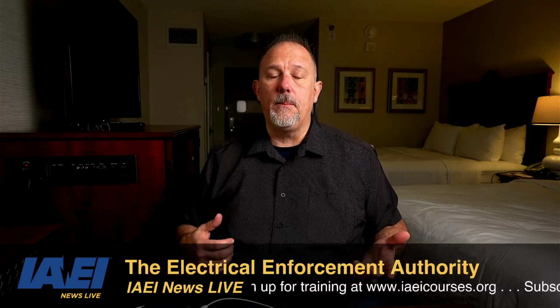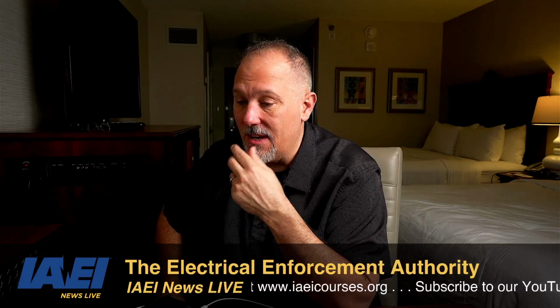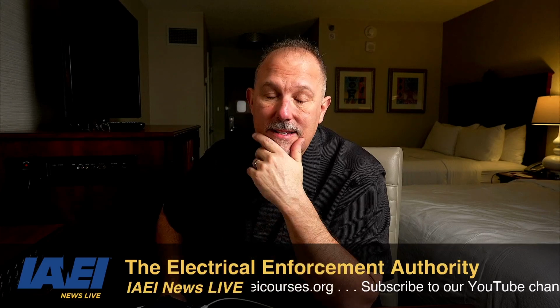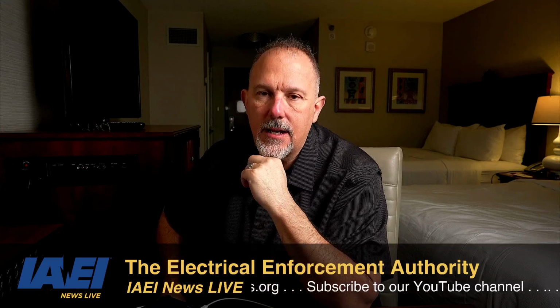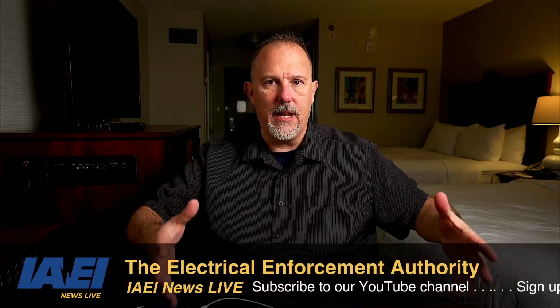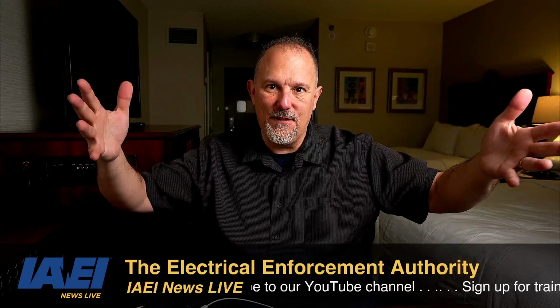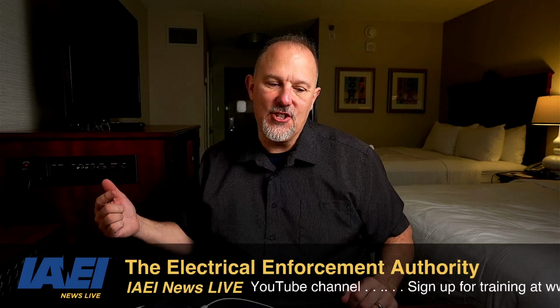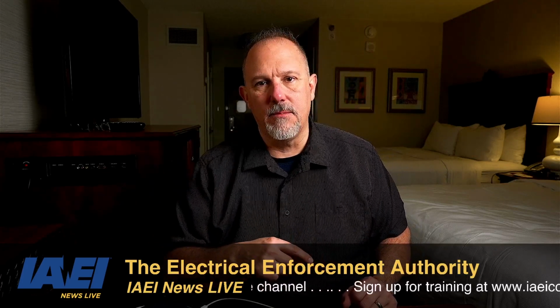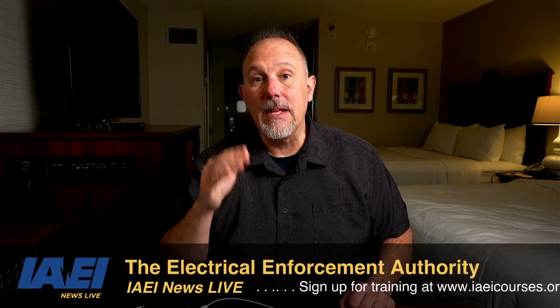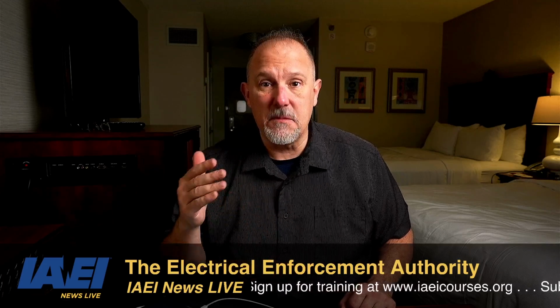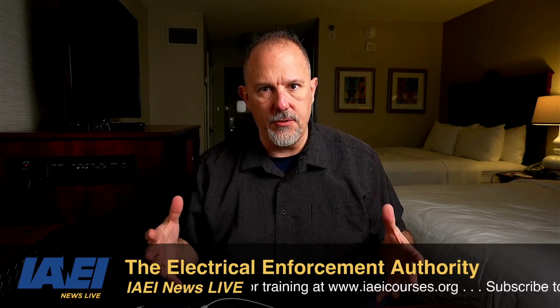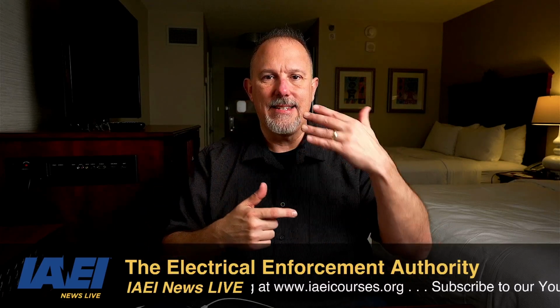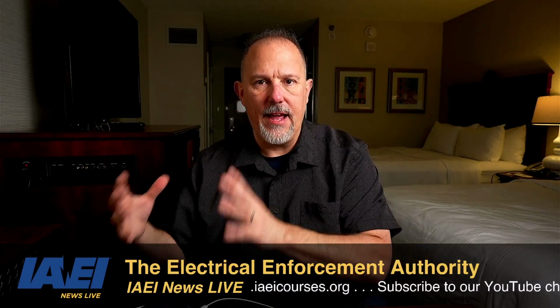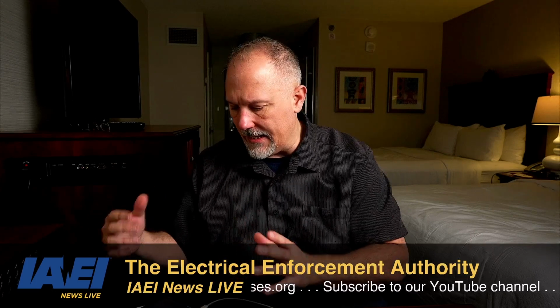Now, is it possible to put a generator indoors? I've seen it done. Believe it or not, it was a residential dwelling unit. It was a very large home for a very rich individual. They had a humongous generator in the basement in a special area. It was concrete. It had special ventilation fans and a whole bit. They spent a lot of money to put the generator inside the structure. Is it possible? I'm going to say heck yes, because I've seen it done legally. It is very expensive because you have to address all of those concerns and issues around not just the rotor and stator, but the prime mover, whatever is turning that rotor. You've got to consider it as well.